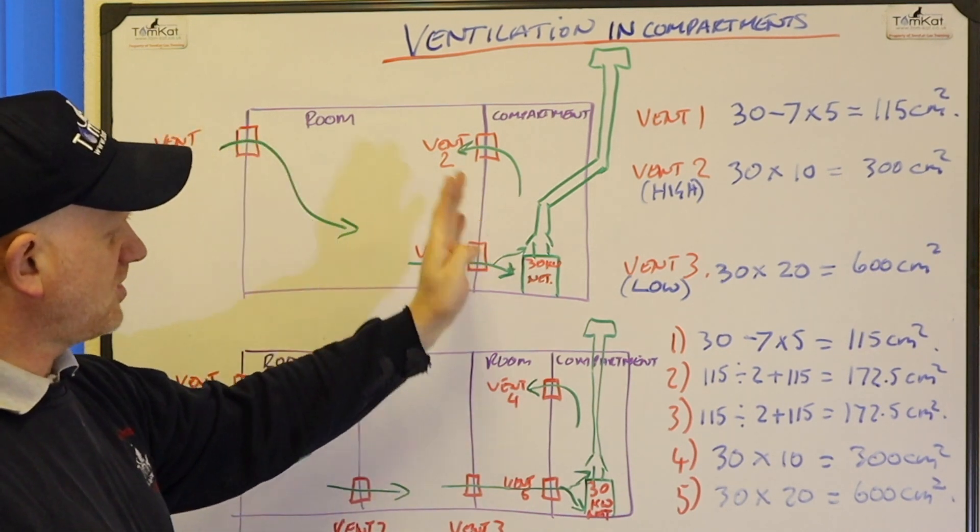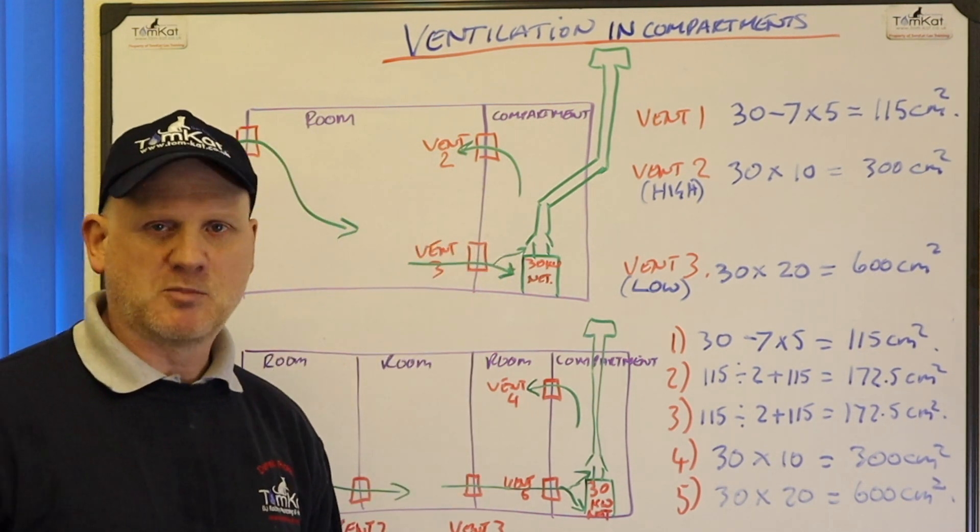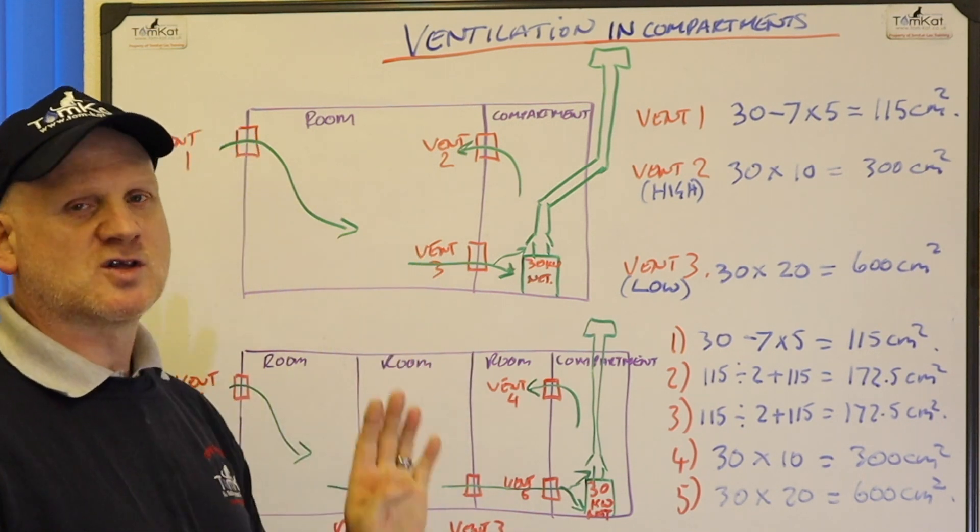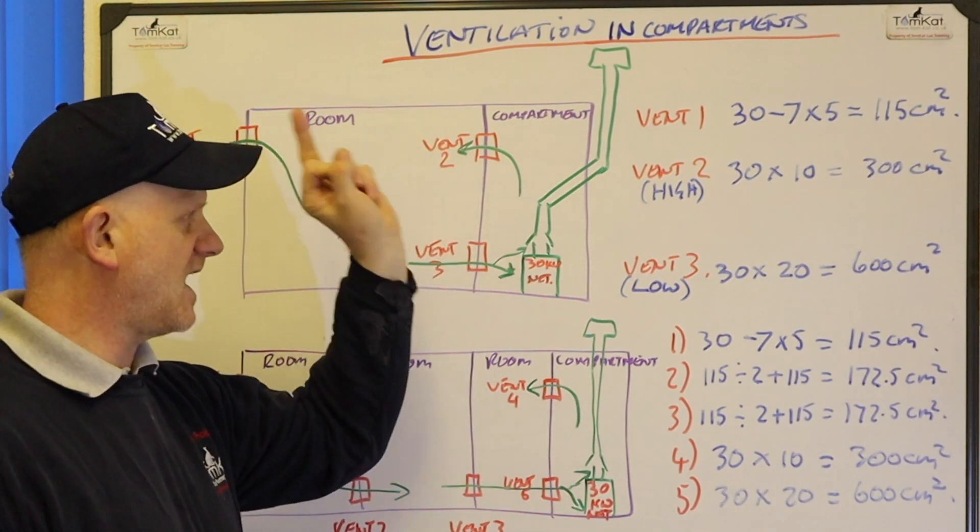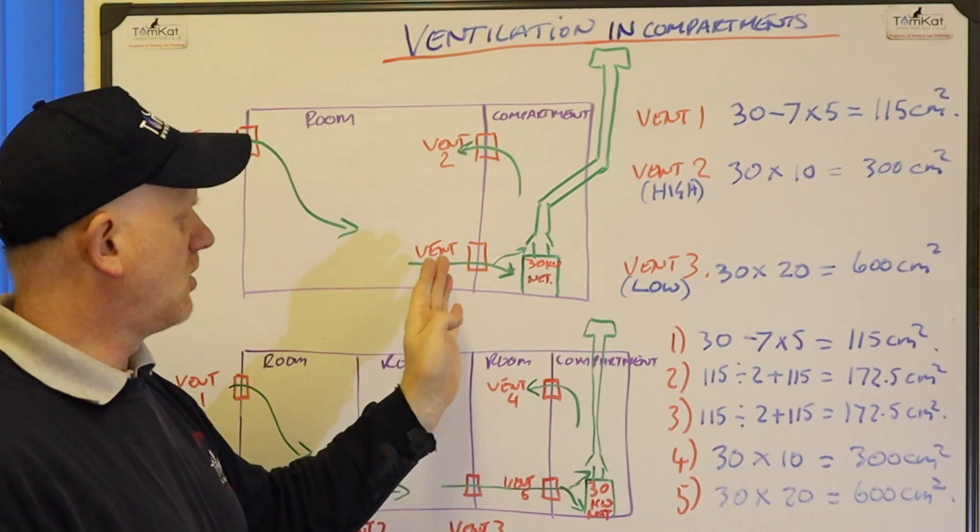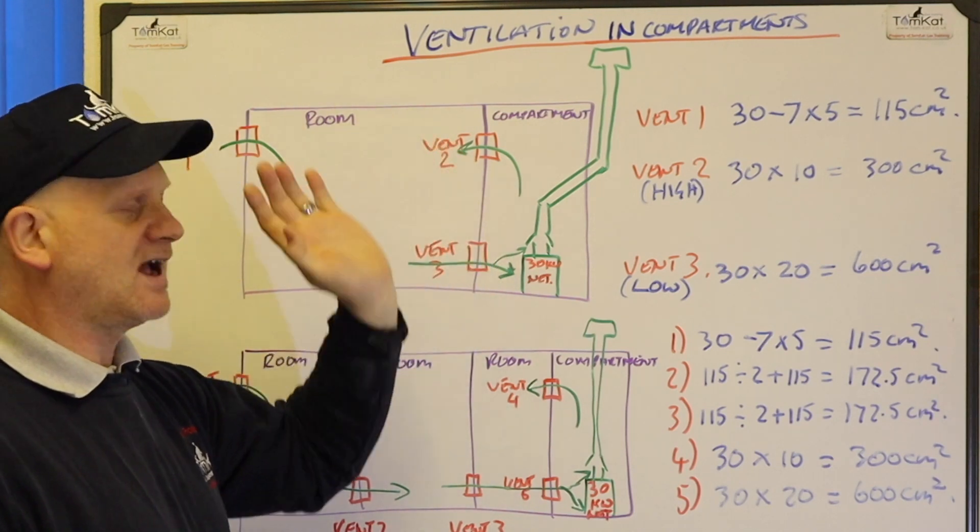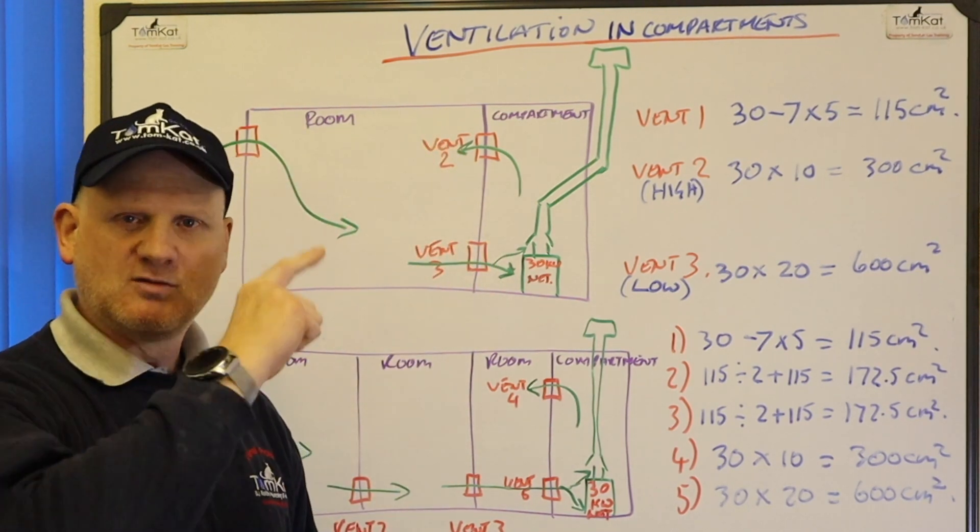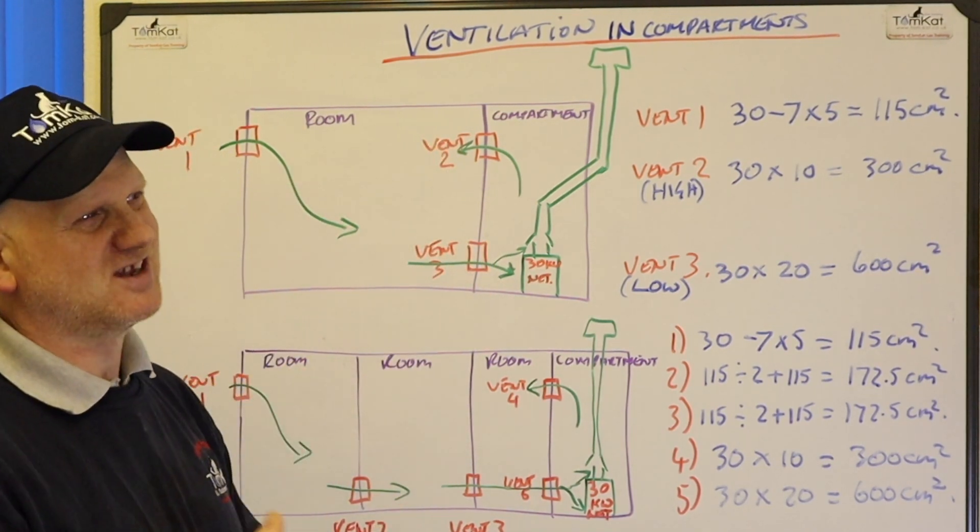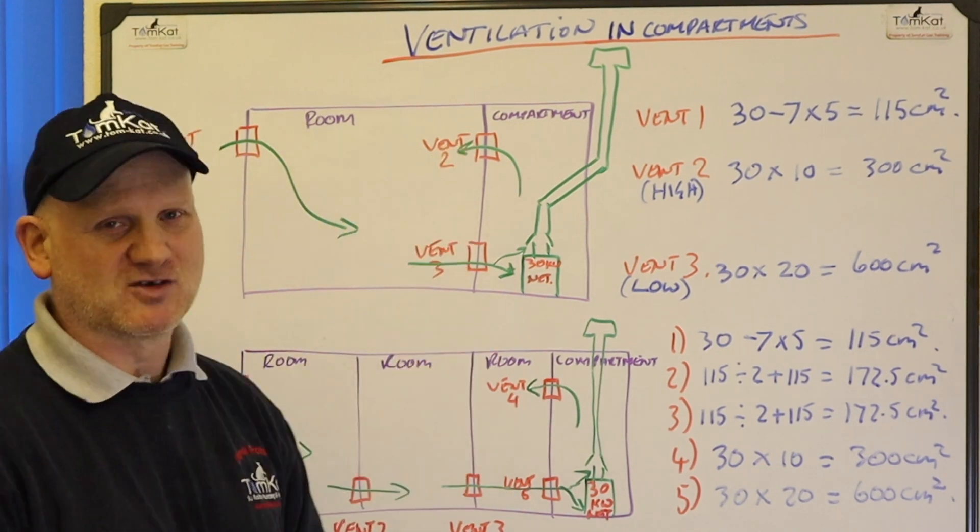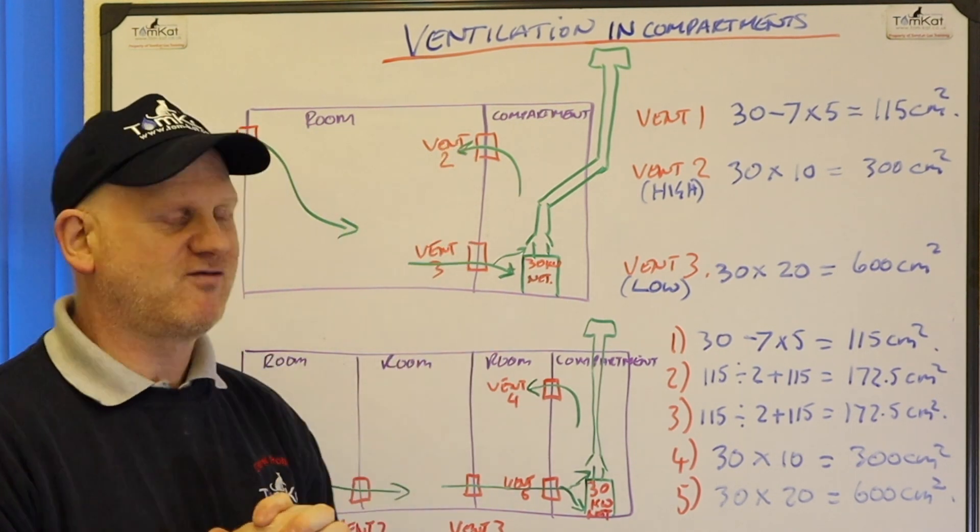And because this boiler is installed in a compartment we require two vents. We need a low level vent and a high level vent. Now the low level vent brings the air in for combustion and the high level vent gets rid of the warm air. It does actually help a little bit with bringing air in for combustion but it's mainly there for cooling.